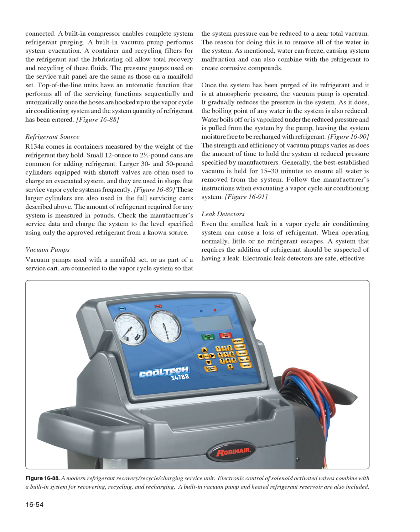A built-in compressor enables complete system refrigerant purging. A built-in vacuum pump performs system evacuation. A container and recycling filters for the refrigerant and the lubricating oil allow total recovery and recycling of these fluids. The pressure gauges used on the service unit panel are the same as those on a manifold set. Top-of-the-line units have an automatic function that performs all of the servicing functions sequentially and automatically once the hoses are hooked up to the vapor cycle air conditioning system and the system quantity of refrigerant has been entered.